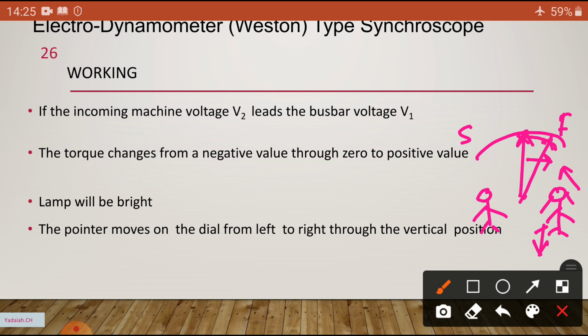So that is the meaning: if the incoming machine voltage V2 leads the bus bar voltage V1, the torque changes from negative through zero to the extreme right, and the lamp brightens. The pointer moves on the dial from left to right through the vertical position.